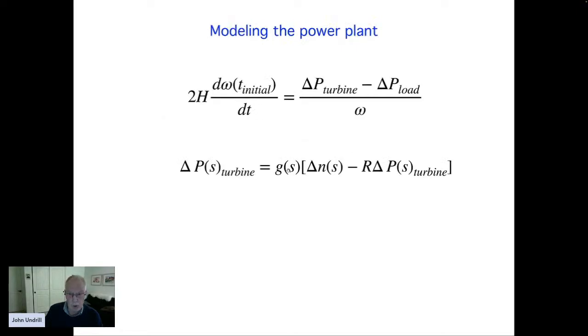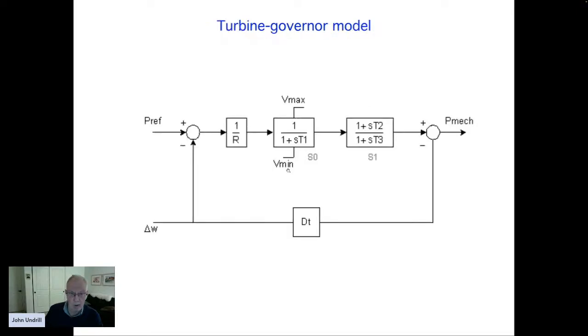This transfer function, G of S, the transfer function of the power plant, for a steam turbine could be as simple as this. Here's the droop, R. This is a gain of 20 if the droop is 5%. Time constant of valve motion. This is a mechanical linkage that's moving a steam valve in response to the motion of a governor. The governor today is electronic, but 20 years ago it was still a mechanical flyball governor. And this is the dynamics of perhaps the steam turbine and the boiler.